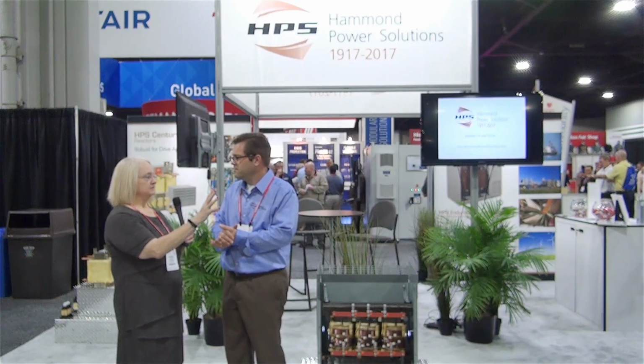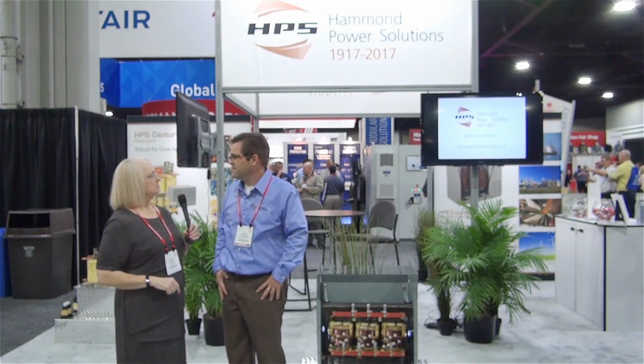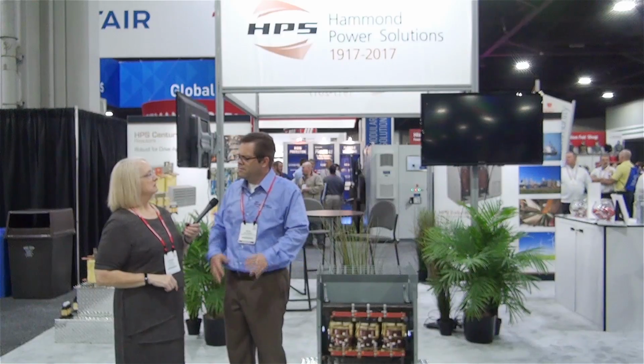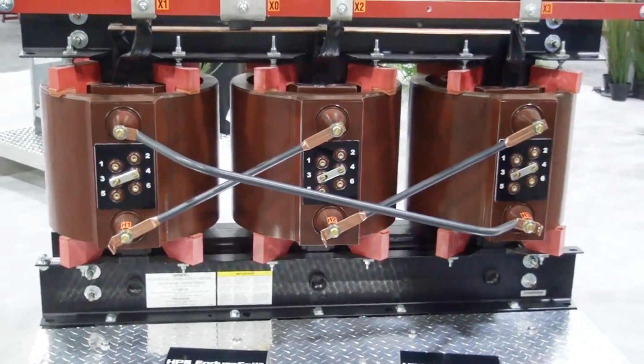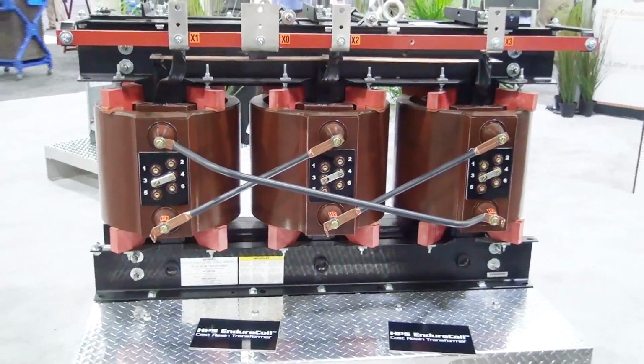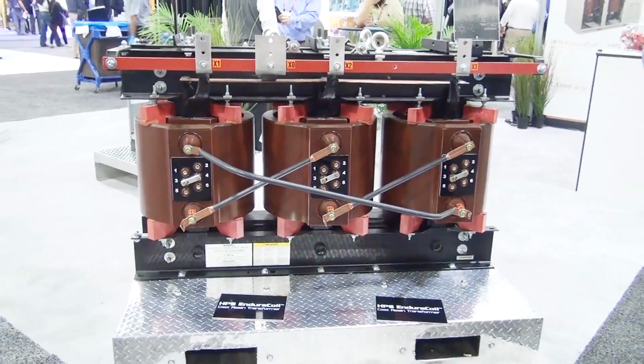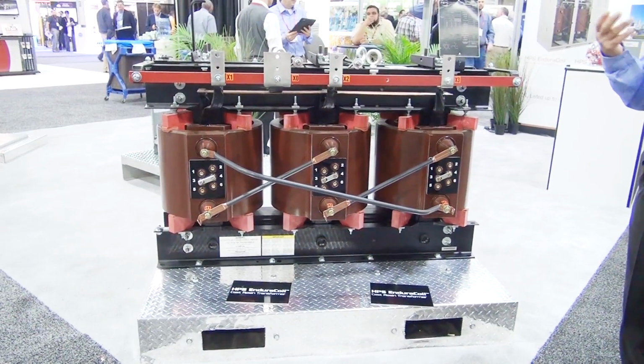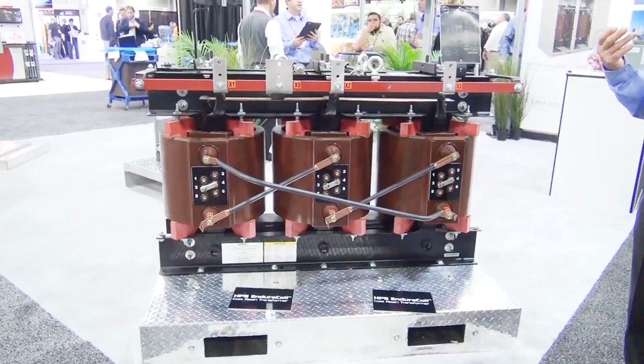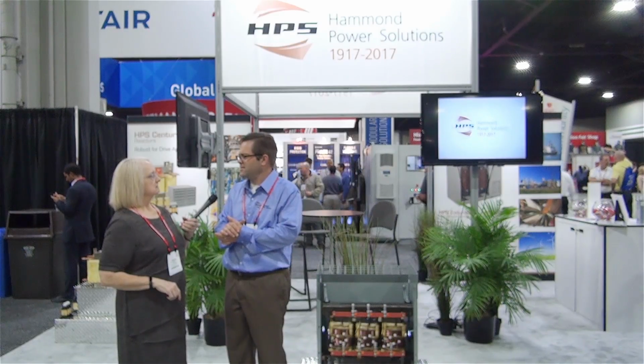There's also a lot of attendees hovering around this other product here. The larger transformer off to my left is what we call a cast coil transformer, an example of a medium voltage transformer. You can tell because it's a lot larger, bigger. The other big difference is that it uses a casting process.